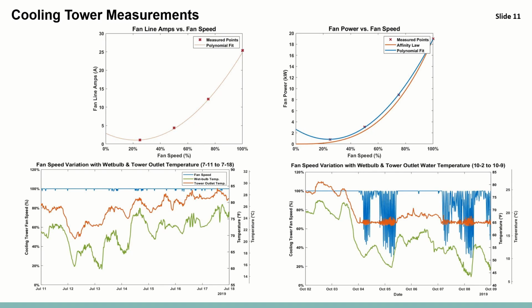Furthermore, the fan speed variation with relationship to the wet bulb temperature ended up being important. So in the graph on the bottom left, we can see that the fan operates at 100% speed for most of the year, as long as the tower outlet water temperature remains above the set point of 65 degrees Fahrenheit, at which point the cooling tower fan would begin to cycle between its minimum and maximum speeds, maximum being 100, minimum being 25% speed, in order to maintain the condenser water temperature around the set point of 65 degrees Fahrenheit. The difficulty with this is we had to remove a lot of data from our cooling tower model because the cycling of the cooling tower fan creates a non-steady state system, and we couldn't model that with the technique that we used.